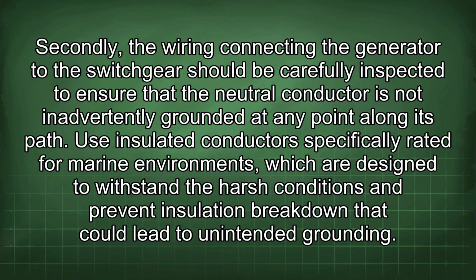Secondly, the wiring connecting the generator to the switchgear should be carefully inspected to ensure that the neutral conductor is not inadvertently grounded at any point along its path. Use insulated conductors specifically rated for marine environments, which are designed to withstand the harsh conditions and prevent insulation breakdown that could lead to unintended grounding.